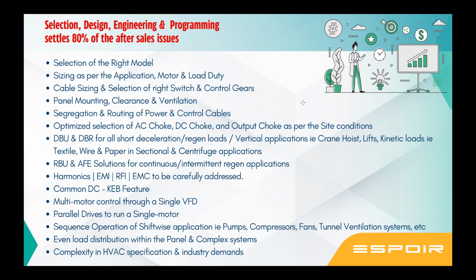Then there are certain cross-section applications where you need to be very careful, such as textile, wire winding, paper, where one motor is going to be in motor mode and another motor is going to be in regeneration mode. So you need to really balance it. Centrifugal applications are again crucial. There is something called a KEB feature, kinetic energy buffering, where in such applications this kinetic energy is going to be present. We can use it very effectively. Regeneration can feed power to the motor which is in motor mode.